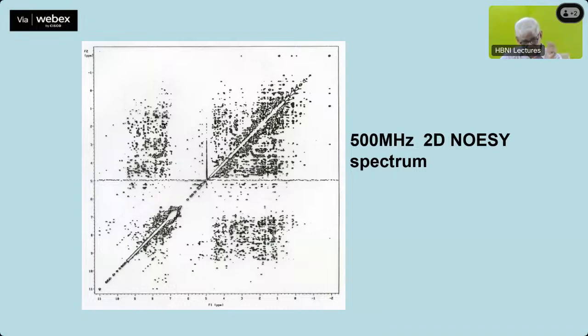However, when you go to such large magnetic fields, you also have additional complications due to chemical shift anisotropy and line broadening because of that, and so on. They are also very expensive, not easily accessible, not easily available. But by and large, 700, 800 megahertz spectrometers are available in many places, so one can go to that. When you go to higher magnetic field, the dispersion will increase a little bit more, so you can go to somewhat higher molecular weights, and this is actually a lysozyme spectrum.